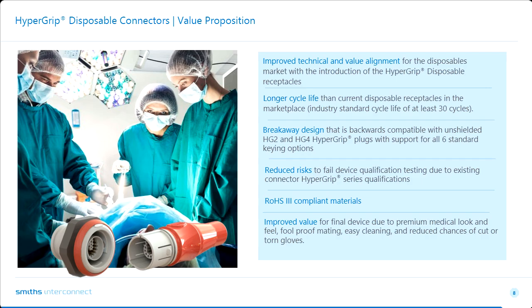Longer life cycle than other incumbent disposables offerings. A lot of times you'll see anywhere from 5 to 15 cycles. Like I mentioned, we went up to 30 just to give that extra factor of safety. The breakaway design, which we also call a passive latch, means that if there's a pulling force applied, the connector will disengage rather than hold on to its mating connector, which in the disposables market segment is really critical to make sure that you're not accidentally pulling something that's attached to a patient.